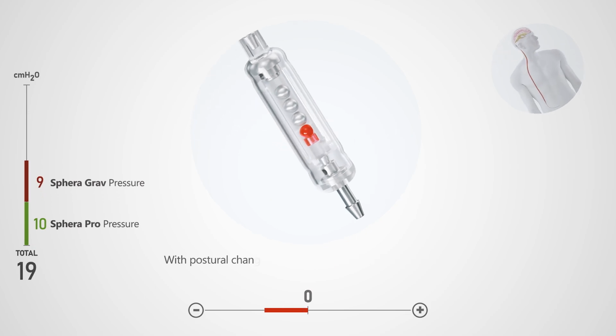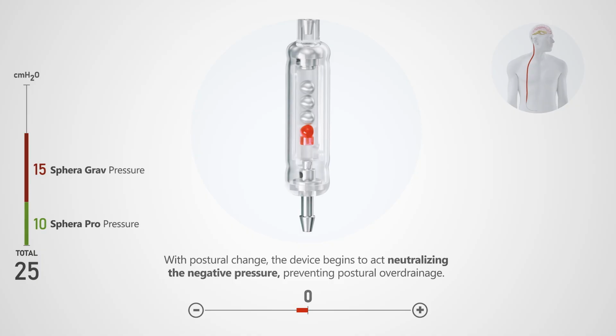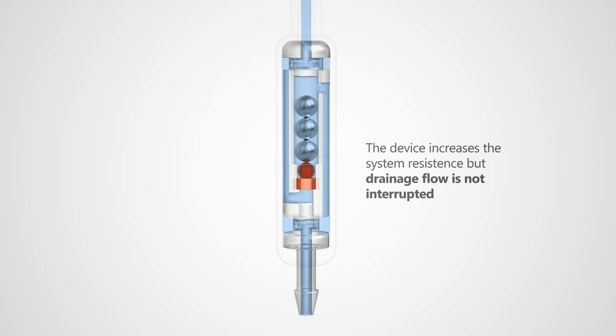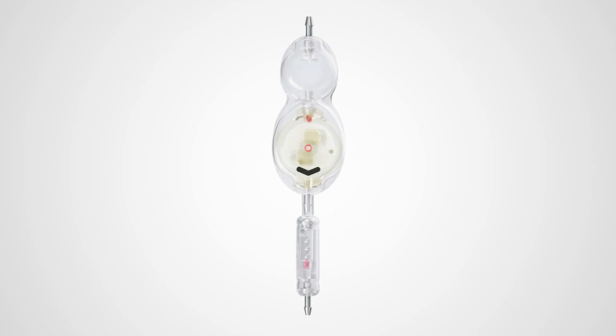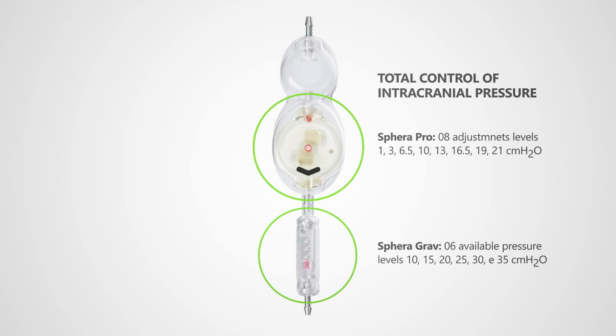However, with the postural change, the anti-gravity device begins to act, neutralizing the negative pressure in the siphon effect, thus preventing overdrainage. The weight of the tungsten balls on the ruby ball increases the system resistance, but the drainage flow is not interrupted. The SpheraGrav device pressure should be selected prior to implantation according to the patient's weight and height. The combination of the SpheraPro programmable valve, with 8 settings of pressures, and the SpheraGrav anti-gravity device, with 6 available pressures, provide a genuine intracranial pressure control.